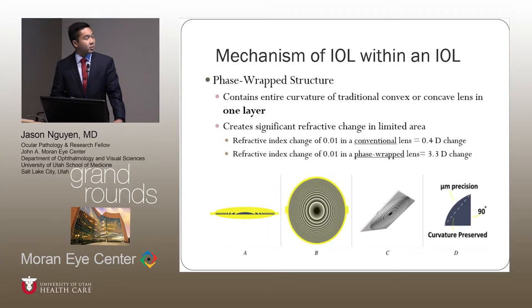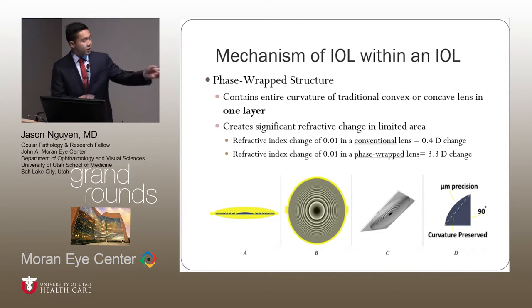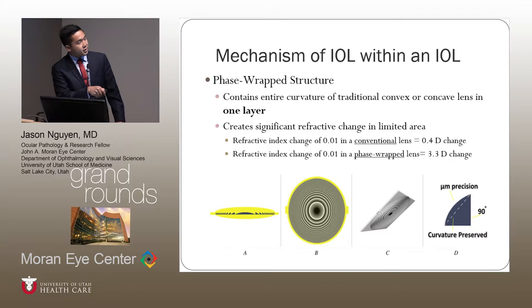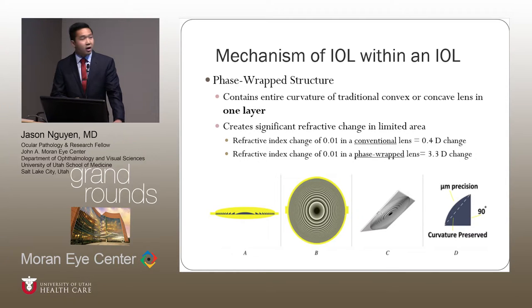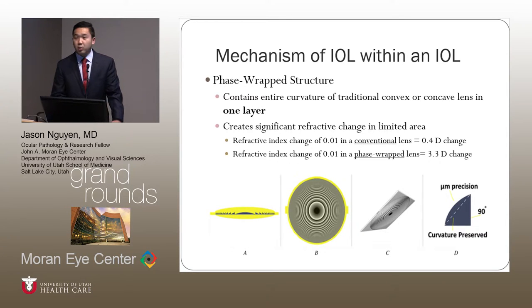What's unique about the phase-wrap structure is that by utilizing this technique, you can contain the entire curvature of a convex or a concave lens in one layer — as you can see in the figure with a side view, top view, and 3D view showing how thin it is. This is important because when you make this IOL within an IOL, you only have about 200 micrometers of space to work with. You're able to have a very significant refractive change in a very small area. With a refractive index change of 0.01 in a conventional lens, you only have about 0.4 diopters change; but with the same index change in a phase-wrapped lens, you have up to 3.3 diopters change.